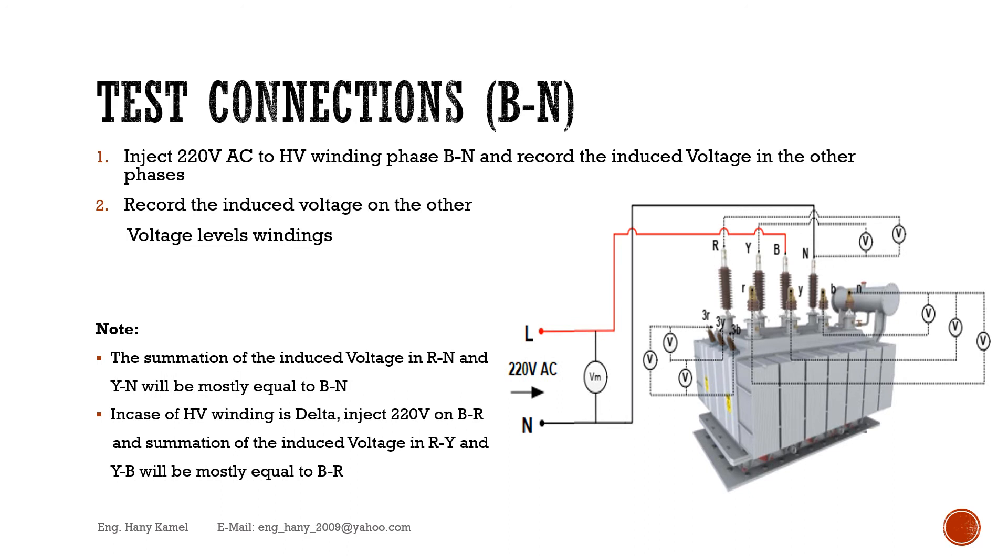Inject 220 volt to HV winding phase B-N and record the induced voltage in the other phases. Record the induced voltage on the other voltage level windings. Note: The summation of the induced voltage in R-N and Y-N will be mostly equal to B-N.